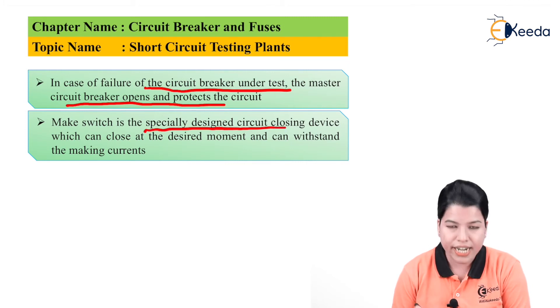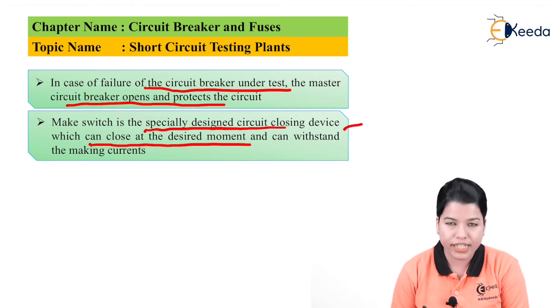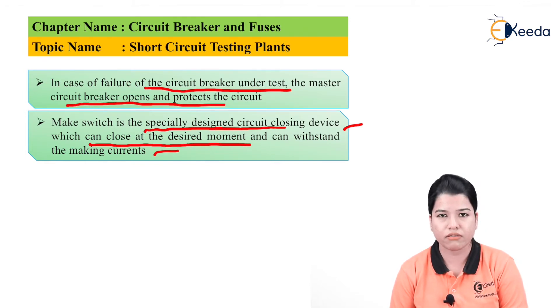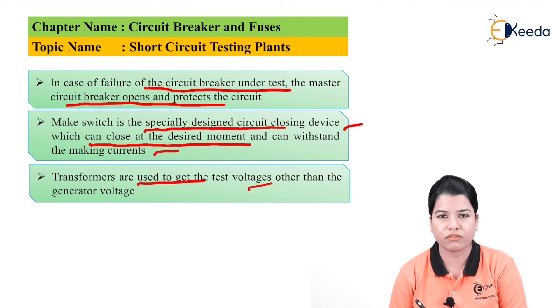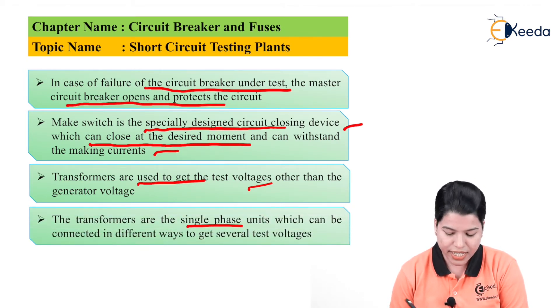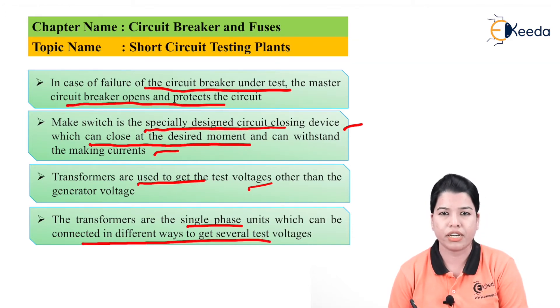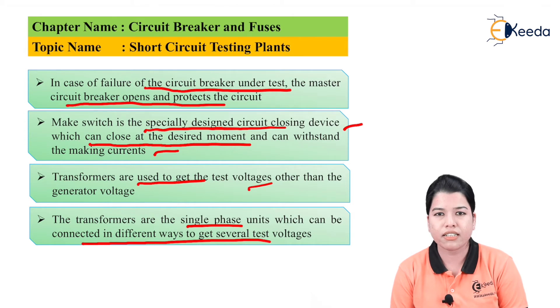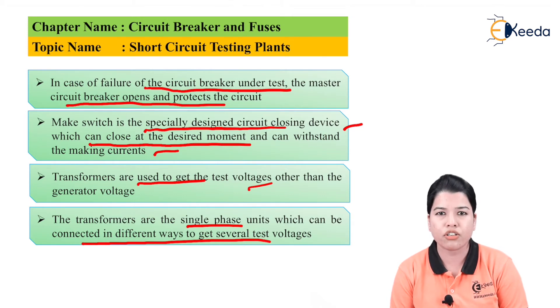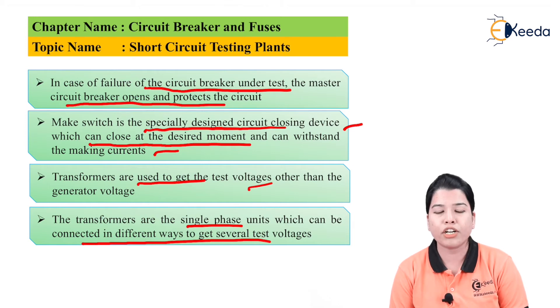The make switch is a specially designed closing device that can close at the desired moment and can withstand making currents. Transformers are used to get the test voltage other than the generated voltage; they are single-phase units that can be connected in different ways for several tests. A step-down transformer is used if lower voltage is needed, and a step-up transformer if higher voltage is needed, adjusted according to the requirement of the circuit breaker under test.